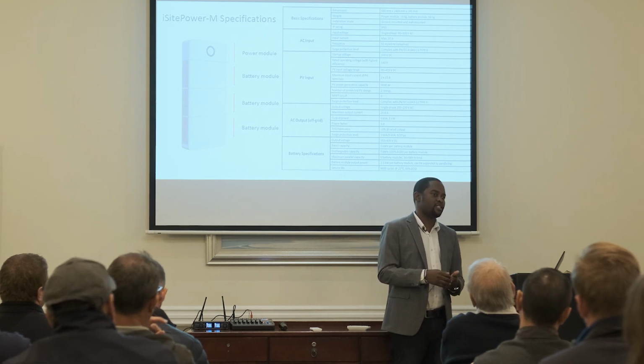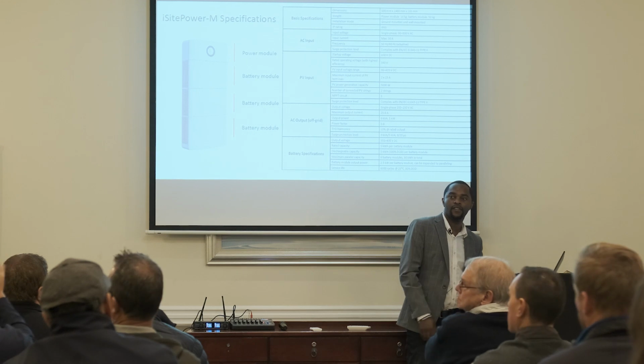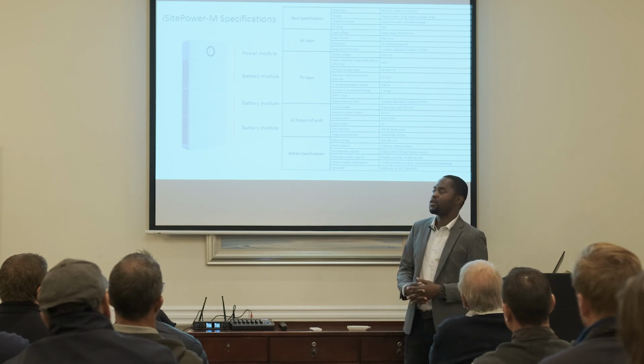So the cells can actually support that, but the BMS is limiting the cells to 0.5C on the discharge. All right. Because it's such an enclosed unit, the neutral earth bond in off-grid mode, does it have that? So it has got those dry contacts. I'm going to look at that also in the next few slides.